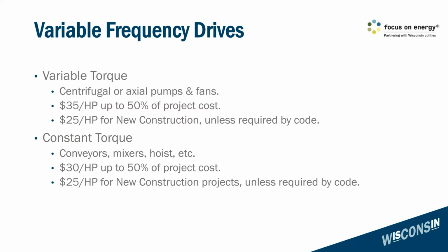But we do have 2 types for the prescriptive route: variable torque and constant torque. Variable torque is going to be for, say, centrifugal or axial pumps and fans - we pay $35 per horsepower, up to 50% of the project cost. Something to note is we pay per horsepower of the motor controlled. So if for some reason the VFD that you're installing is sized a little bit larger than the motor is, we pay for the motor that's being controlled by that VFD.